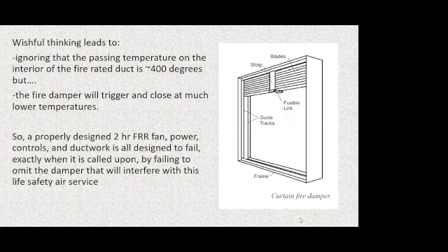So we can't have something on that unexposed side, on the inside, that we need to be moving air during the fire that's going to close and render the system non-functional. And we'll talk about what we're supposed to do rather than do that. What's important is that what we do as an alternative to that fire damper needs to provide the equivalent alternative protection to what the fire damper was going to do. Equivalent and alternative are terms that are going to come up a lot, and there's a reason for that.